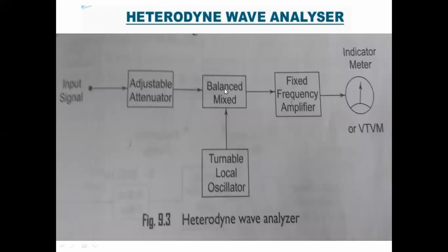This is the basic heterodyne wave analyzer. Mixing of the two signals produces the intermediate frequency, and that intermediate frequency component is amplified by a suitable amplifier and converted into a voltage readable signal.